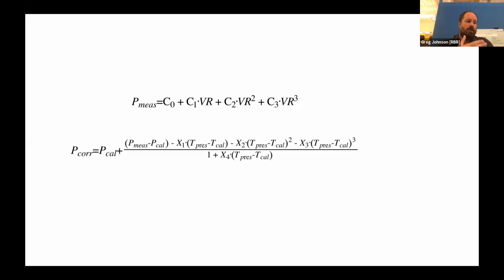Now, that doesn't mean to say that they drift without bounds. We've done quite a lot of work on drift. Temperature typically over the decades will stay within about 10 millik. So it started off with a 2 millik accuracy, and it will drift about 5 times that level, but it just kind of taps out and stabilizes. Pressure is a bit more drifty, and those figures often occur over the course of a year that you'll see that.